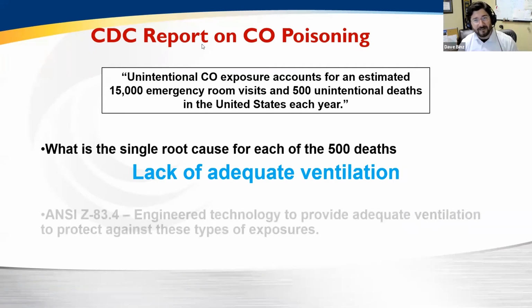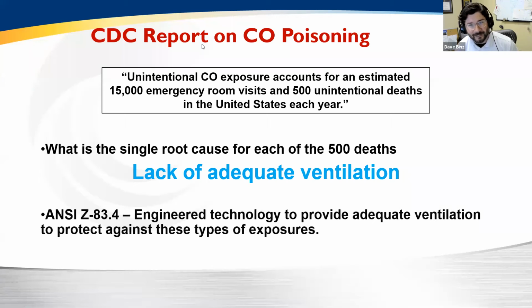And what this technology has, and why it makes it inherently safe, is that I cannot separate the combustion airstream from the ventilation airstream. I am always ventilating as long as I am heating. So I already have extremely low discharge of any kind of CO or combustion byproduct, but I'm always ventilating and always diluting those products, which is why direct fired 100% outside air systems are actually inherently safer than recirculating indirect fired systems.